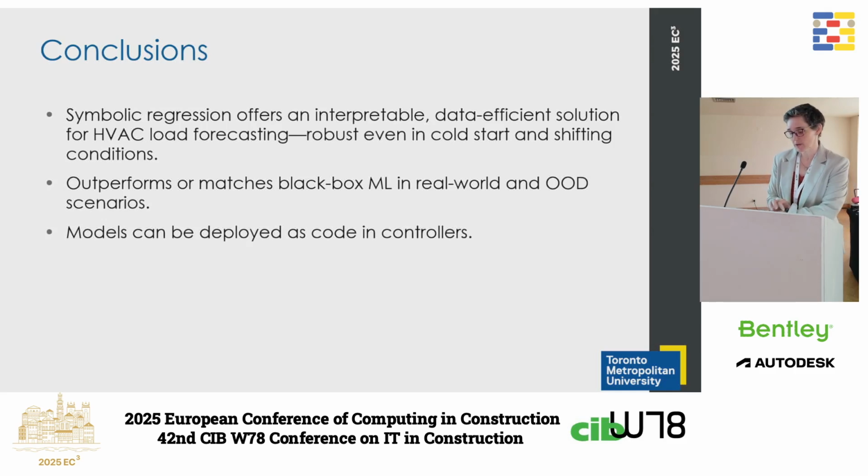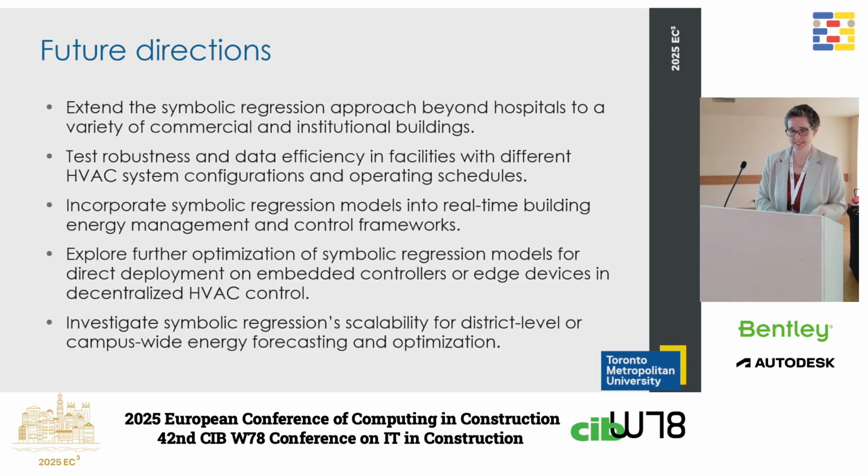So just to quickly summarize, our symbolic regression basically gives us a robust approach where we can actually do load forecasting. This is just one part of a bigger project where we have an emulator for the chiller, the cooling tower, the cooling plant that we're in the process of deploying across a series of hospitals across Canada, so we can test more generalizability. And this is very easy to control locally on a controller. One of the big goals was to simplify this as much as possible to allow field implementation.